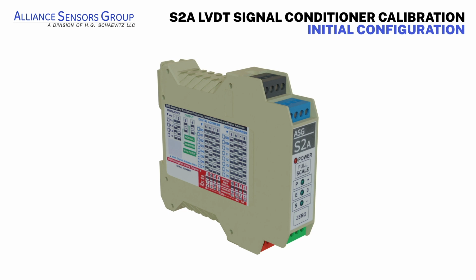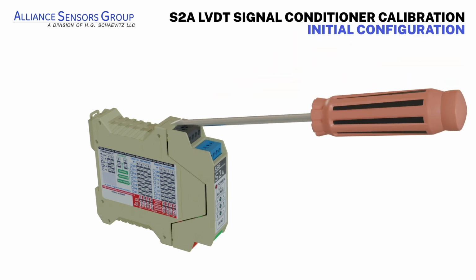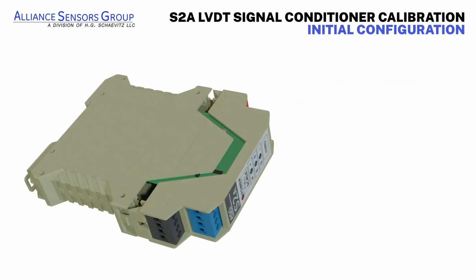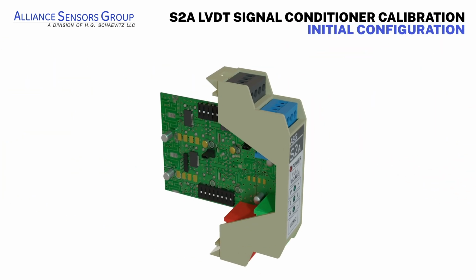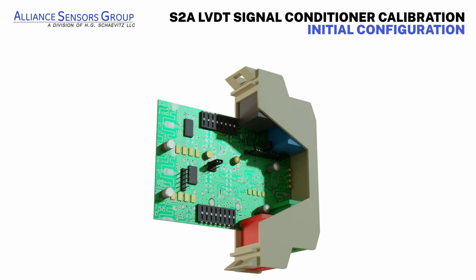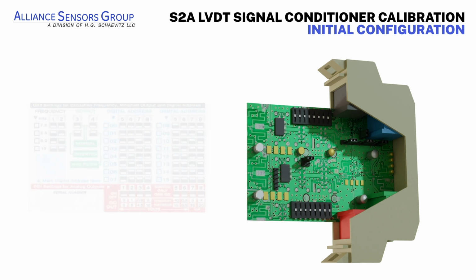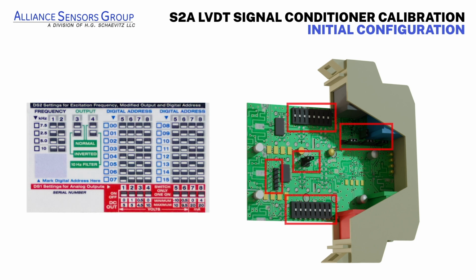However, in the event that your LVDT requires different settings from the factory defaults, you'll need to configure the S2A to match your particular requirements. To perform these adjustments, carefully push in the tabs on both the top and bottom of the signal conditioner's case with a small screwdriver. Then slide the board out from the case to provide access to the dip switches and jumpers. Consult the label on the case or the S2A manual and quick start guide instructions to find the correct dip switch positions and jumper settings for your specific application.